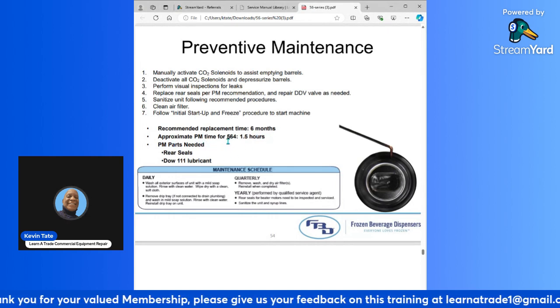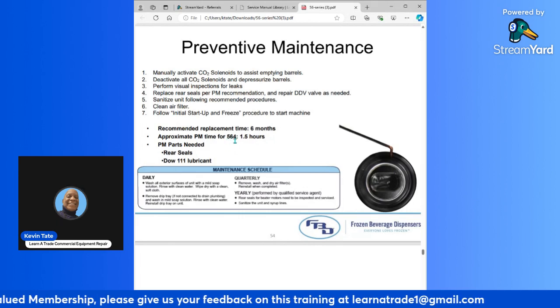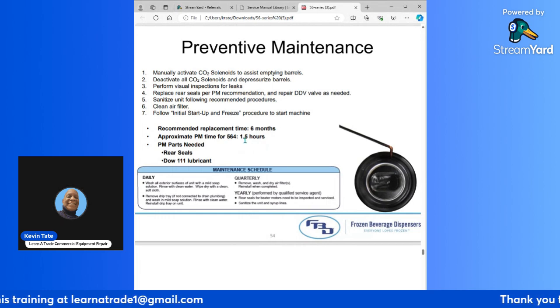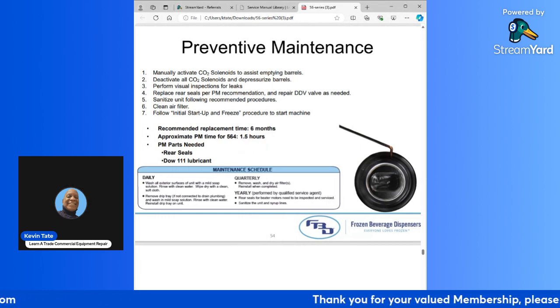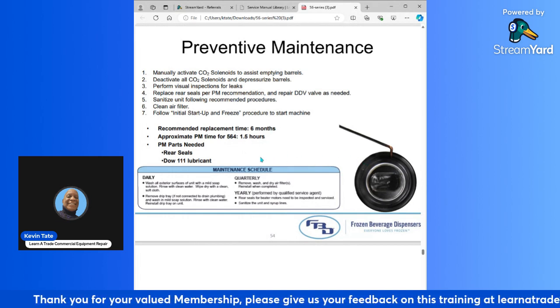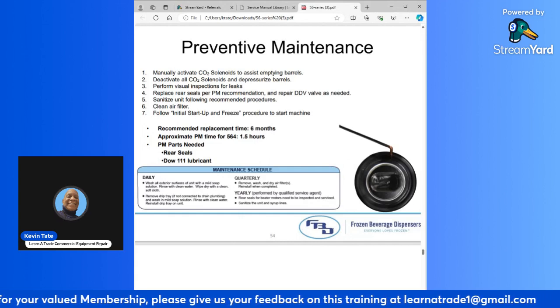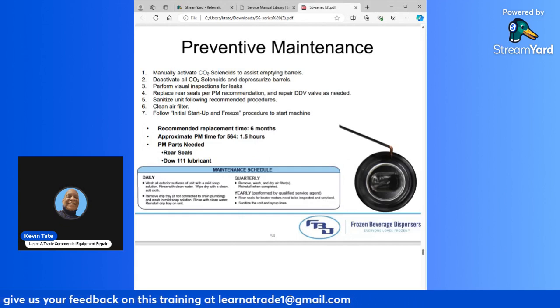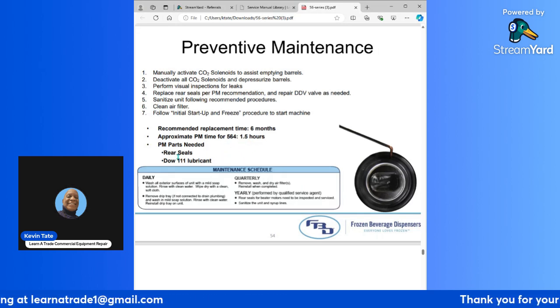Approximate PM time to finish a PM on a 564 is an hour and a half that they have it rated for. That can be disputed, because it can take 2 to 3 hours if the unit hasn't been PM'd in the past, and you're doing the job according to their recommendations. It could take longer than an hour and a half, but that's their recommendation.